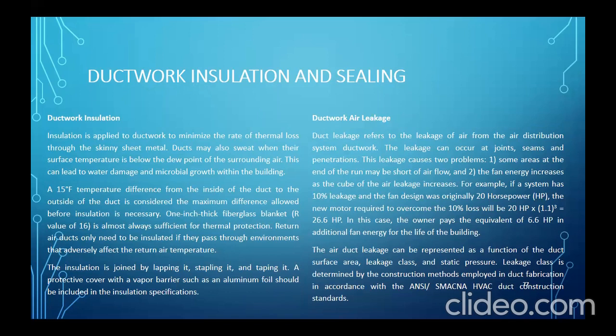So ducts may also sweat when their surface temperature is below the dew point of the surrounding air. So magkakaroon ng condensation, so tutulo yung kisame mo. This can lead to water damage and microbial growth within the building. A 15 degrees Fahrenheit temperature difference from the inside of the duct to the outside of the duct is considered the maximum difference allowed before insulation is necessary.